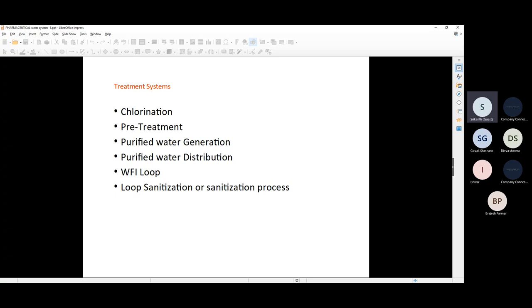In the new approach, we'll also have ozonation loops. Then there's the WFI loop. The purified water distribution loop handles oral solids, but WFI - water for injection - will have hot loops. The purified water distribution loop is an ambient loop, but in WFI we continuously circulate the water above 80 degrees, using a jacketed tank.